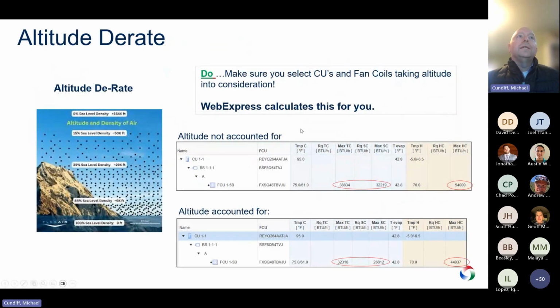Altitude derate. This is another detail specifically for high altitude places like Colorado. Most manufacturers are going to have an altitude derate built into their programs, but make sure you're using that. As you can see at the top here, the altitude was not accounted for. You get close to 39,000 BTUs. Sensible is at 32.2. Your max heating capacity is at 54. When you are accounting for altitude, you can see that drops down to 32,000 for max total cooling, down to 26.8 for max sensible cooling, down to 44.9 for max heating capacity. So this is something that's very important to pay attention to.